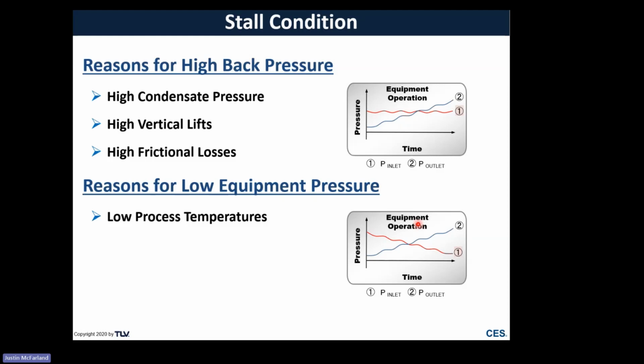It really all depends on the process heating capabilities. But we find most often that with low process heating temperatures, like something below 200 degrees, you might only need near atmospheric saturated conditions. So around 212 or maybe 220 or even 230 Fahrenheit. The corresponding pressures for all that is very, very low. And so once you consider having to return that condensate even to, let's say, an atmospheric receiver, having to move condensate up 20 feet, that equals about 10 PSI back pressure. So that can hinder things to a point where you suddenly thought, okay, I have positive steam pressure, but now you have a negative differential pressure across that drainage device. It's all due to just the fact that there's low process temperature requirements and low BTU requirements.